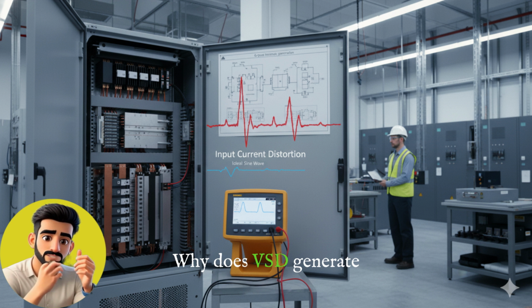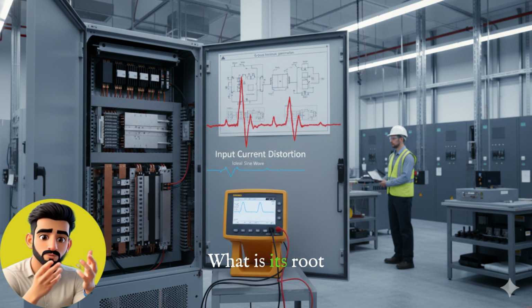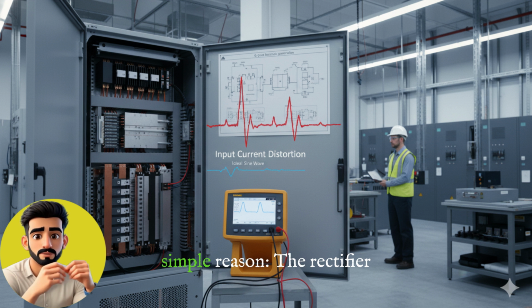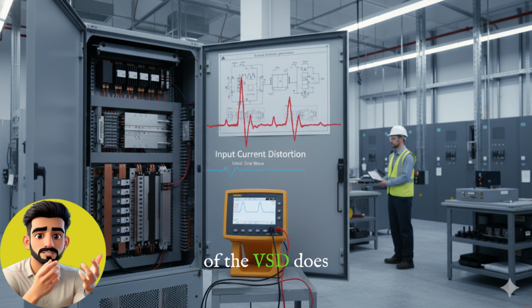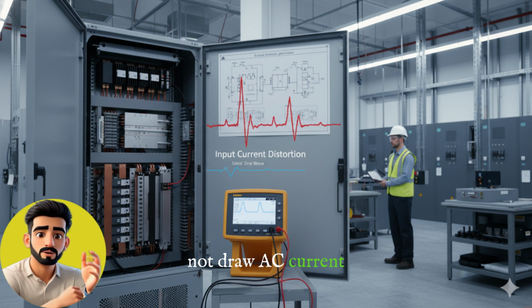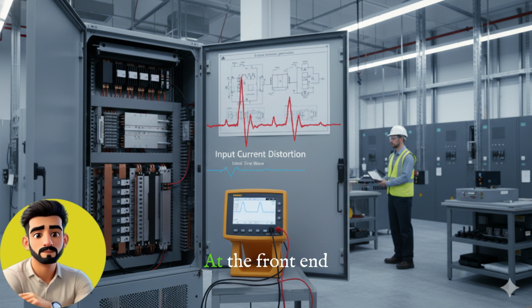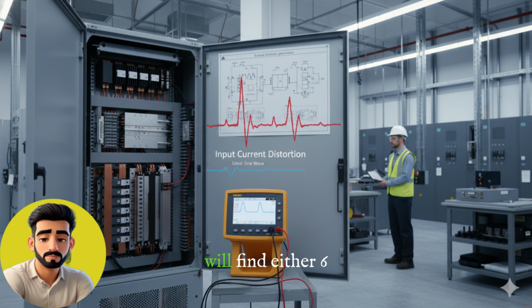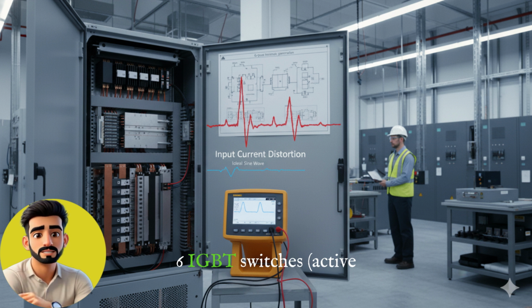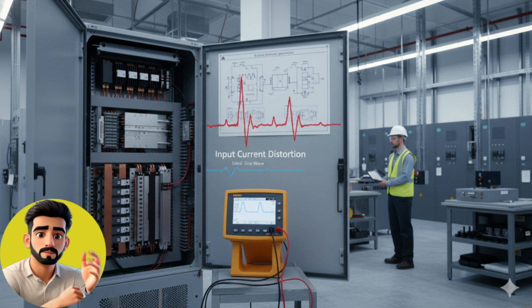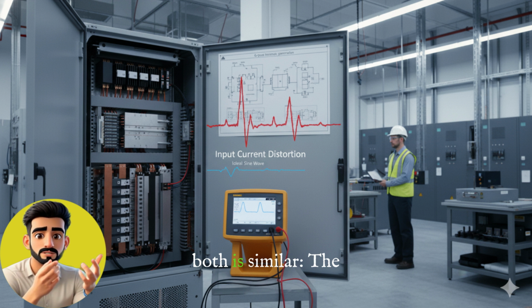Why does a VSD generate harmonics? What is its root cause? There's a very simple reason. The rectifier of the VSD does not draw AC current in a smooth, continuous curve. At the front end of the drive, you will find either 6 diodes, a diode bridge, or 6 IGBT switches, an active rectifier. The working principle of both is similar.